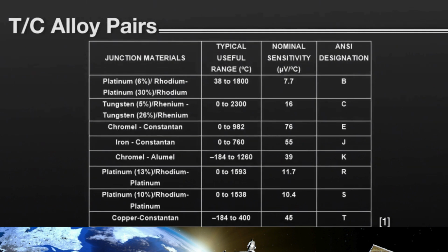Here's a slide summarizing the thermocouple alloy pairs. Some of the materials are pure metals like iron and copper. Most are obscure alloys with names like chromel and constantan. Only a few companies in the world make these alloys, which of course is why I call them obscure. Types K and T allow you to measure very cold temperatures found on the outer planets. Type C is good for jet engines. And the nominal voltage sensitivity is just that. It's nominal. You need to get the actual thermoelectric voltages off the ITS-90 table.